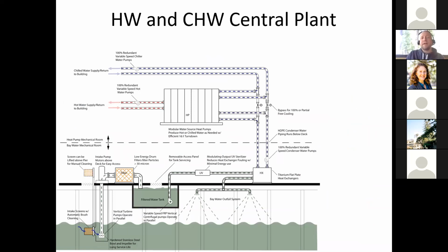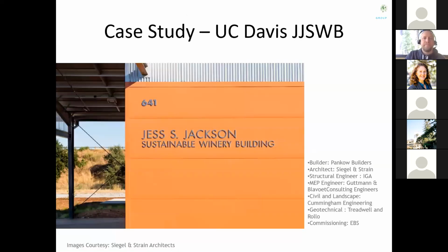Much like a cooling tower, the project can actually do what we call a water side economizer—when the heat pumps turn off, it can just use the bay water directly through the heat exchanger to provide all the cooling. So the heat pumps don't necessarily have to be on, and that makes it even more efficient. When you can run a cooling tower or heat exchanger alone with no heat pump, the efficiency goes up dramatically.